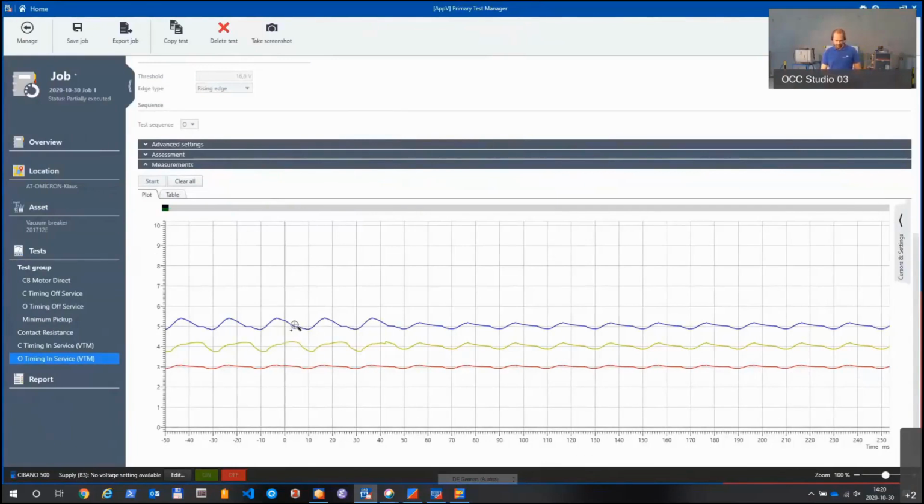Those are not so nice sine waves, as I mentioned. We are using the CMC, not the real values, the real 24 kV. But we clearly see when the sine wave gets stopped and interrupted here. You can even overlay that with the other measurements you did before. So let's do the same for the closing.